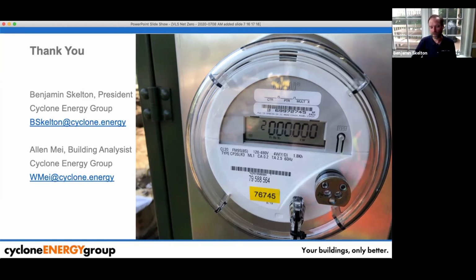From 90% to 100% operation of an LED light, it's the same light output. So if you have a lighting system with LED lamps, especially any kind of fixture like that, you can start it running at 90%, because it's no different light level than it would be at 100%. Similarly, when you get down to 20%, down to 10%, what will happen with that kind of system is you can get into a flickering situation. So it can't just be a 0 to 100 control sequence with lighting. In this case, we had taken it down to, I think, 65% in one area of the building to get the foot candles to where they wanted it, and we took it down to 40% of the full output in another place, and we were able to get the lighting levels.